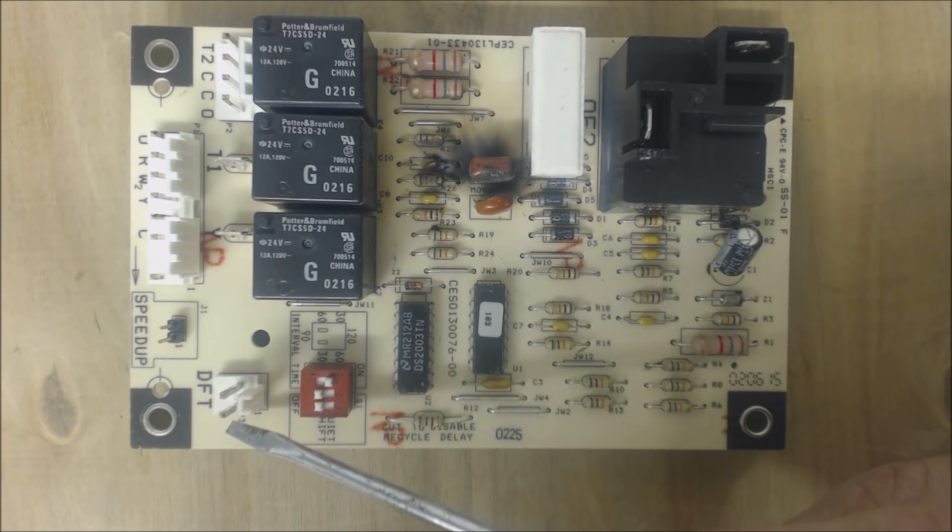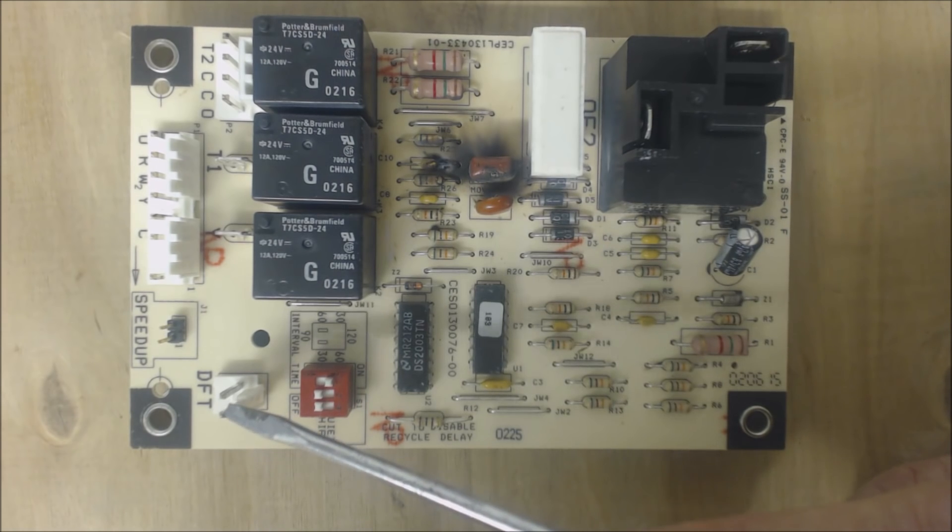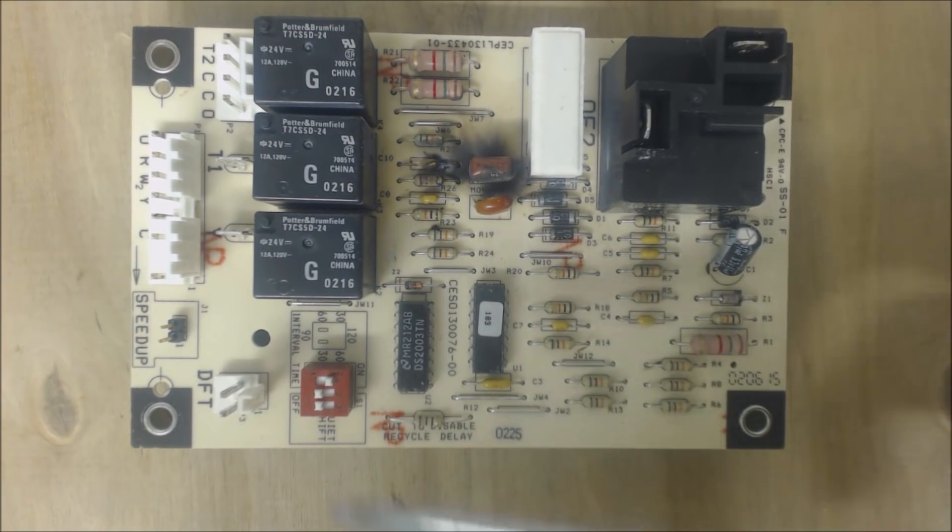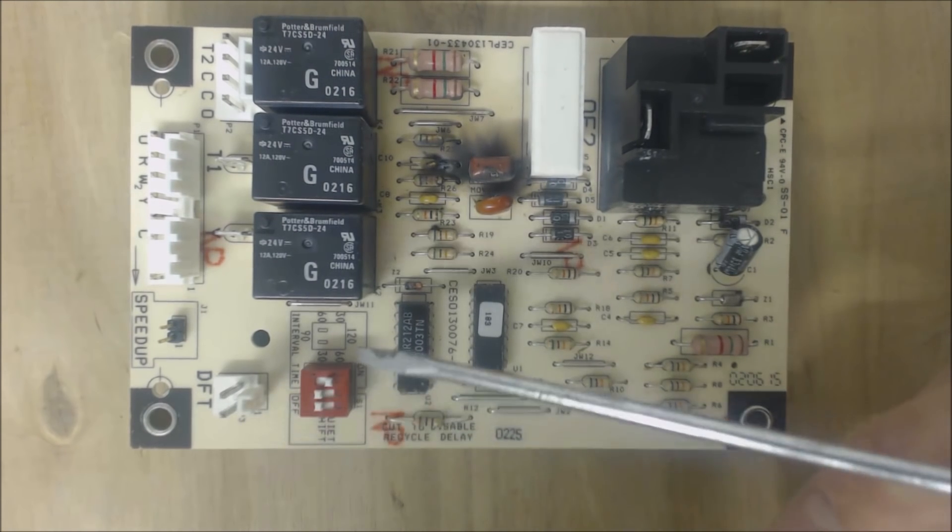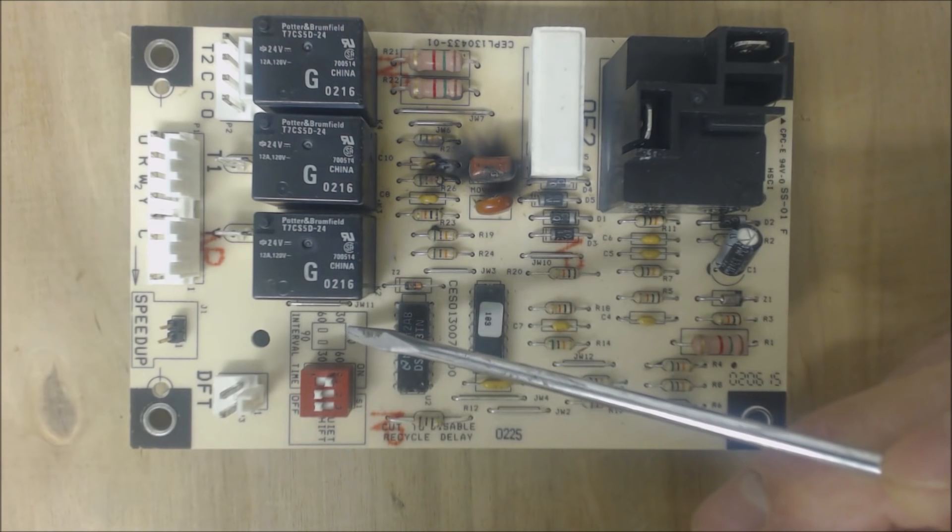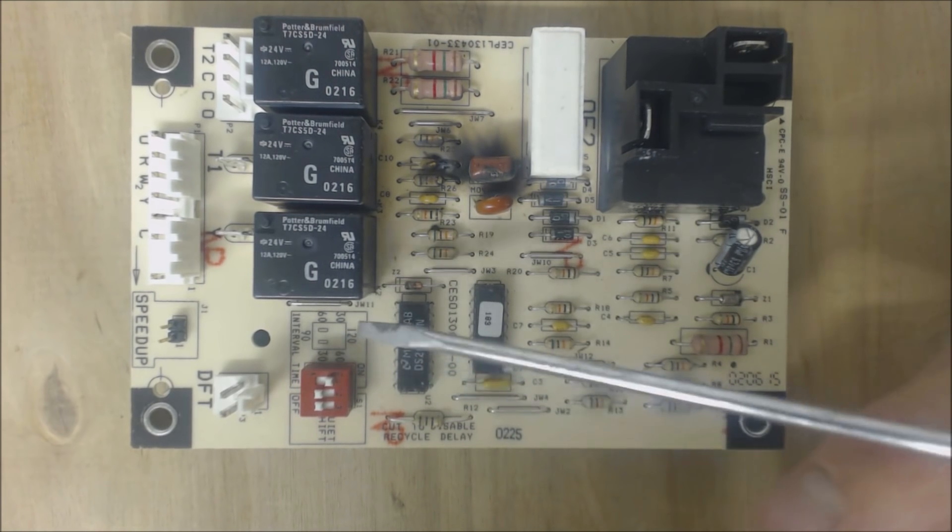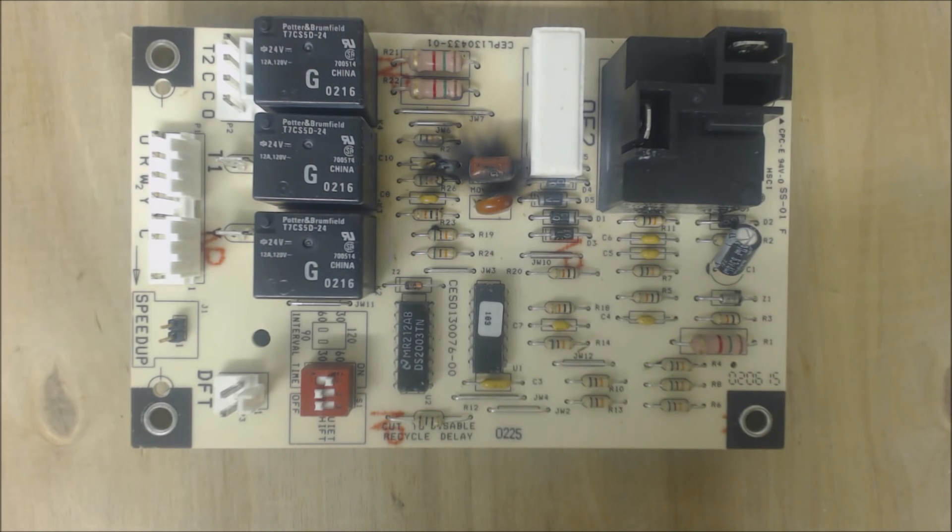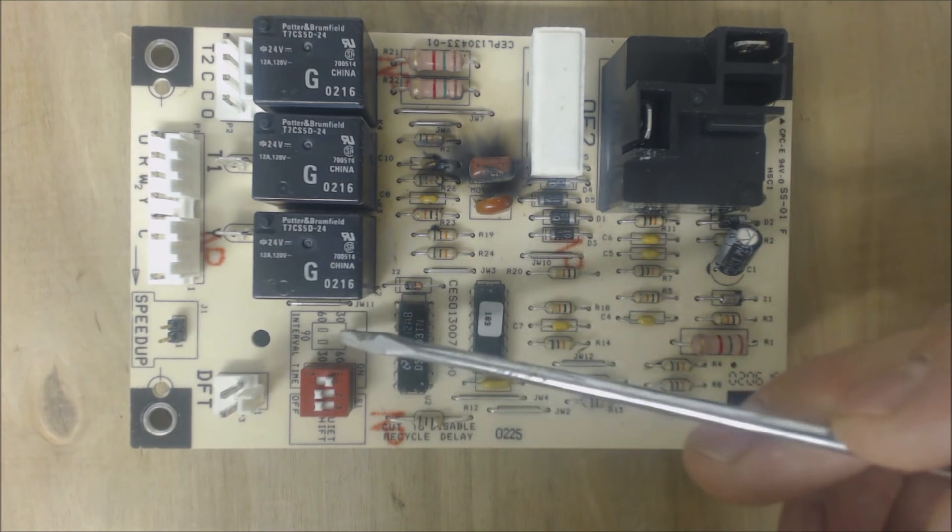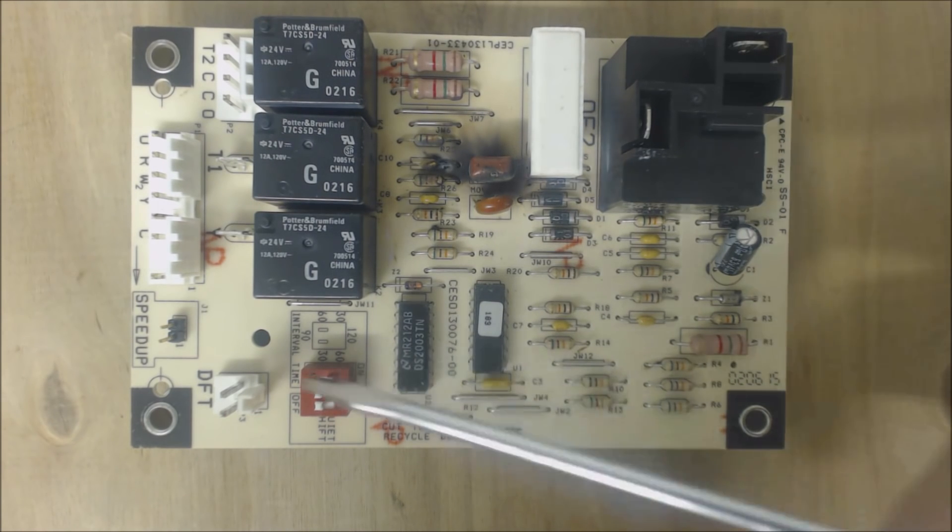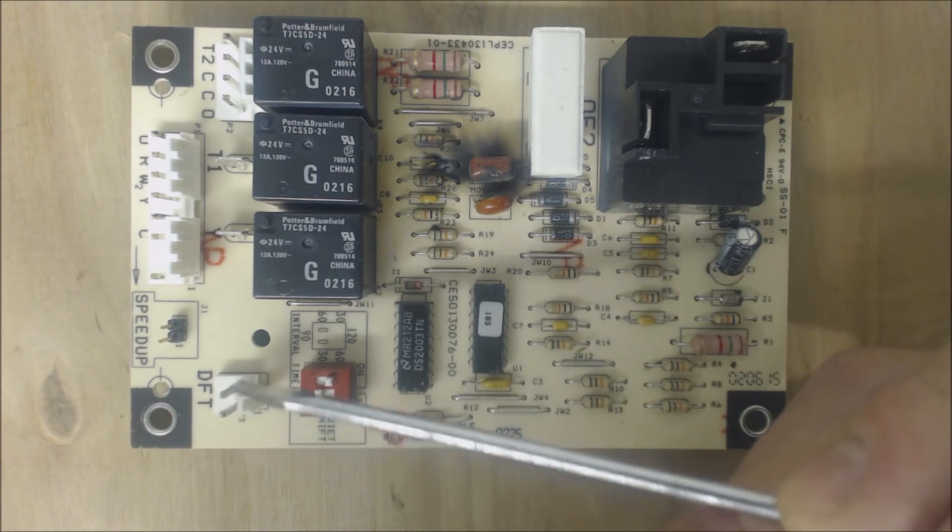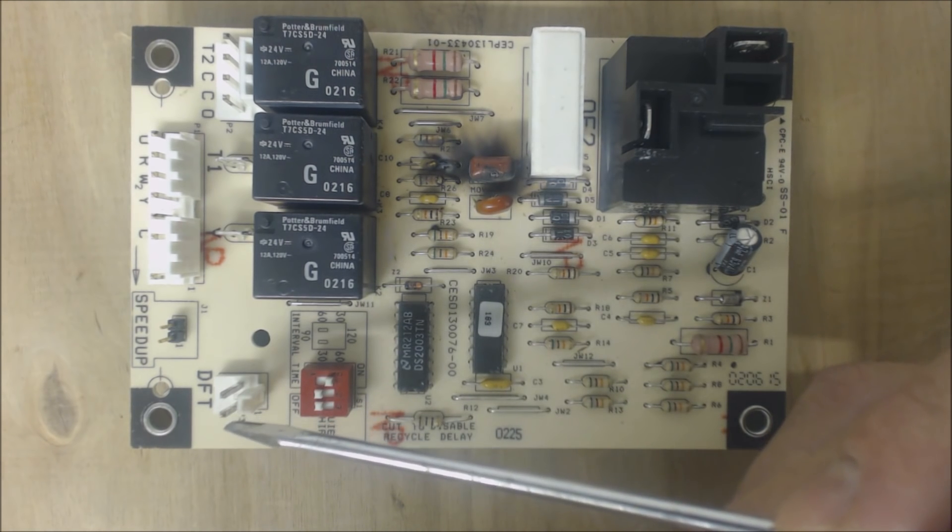Coming off of the DFT, you have a defrost temperature sensor, and that is normally open. So what you have is this is open and this needs to meet the time requirement. So this is a cumulative time requirement. So if the unit shuts off, turns back on, shuts off again, and turns back on, it's basically counting down all of those, you know, whatever the time is, say 60 minutes. It's counting up to 60 minutes. And when it gets to 60 minutes, if this DFT is closed, it's going to enter defrost mode.